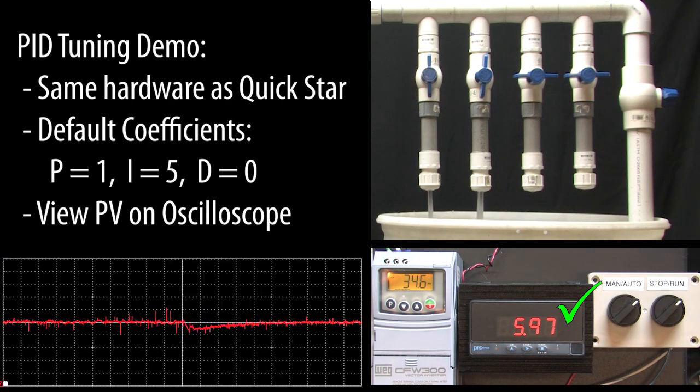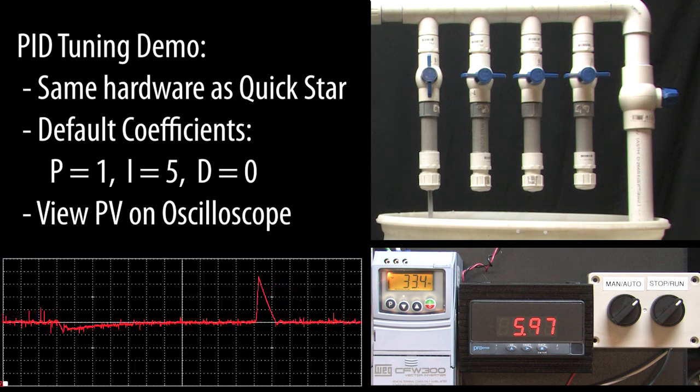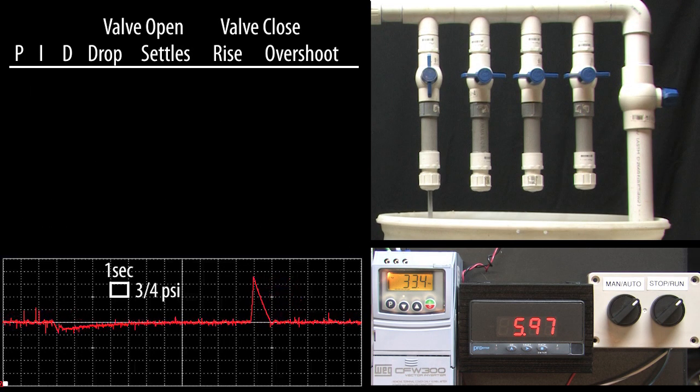I'll close the valve quickly and we see the abrupt pressure increase and then it slowly settles out back at 6 psi over 10-15 seconds. Each of these divisions is 3 quarters of a psi so it looks like the pressure dropped maybe half a psi when we opened the valve and rose 2.5 psi when we closed the valve abruptly.